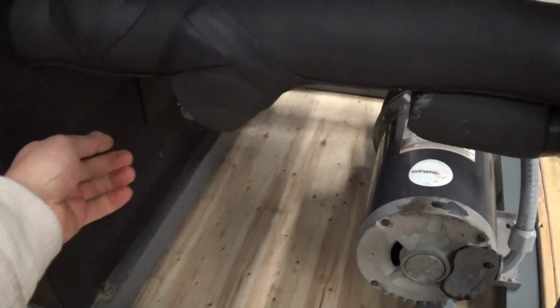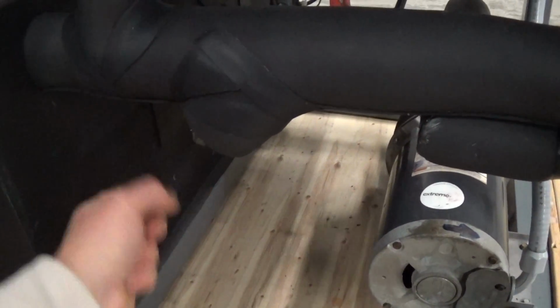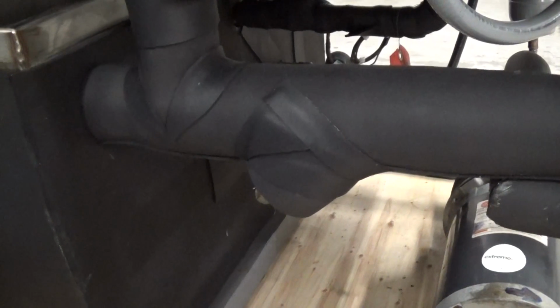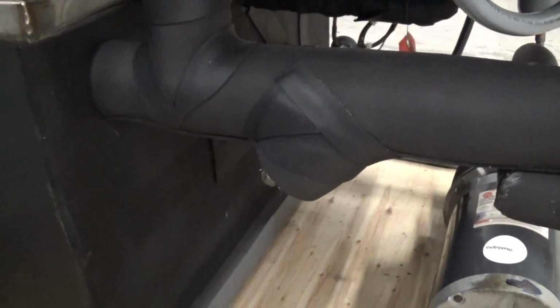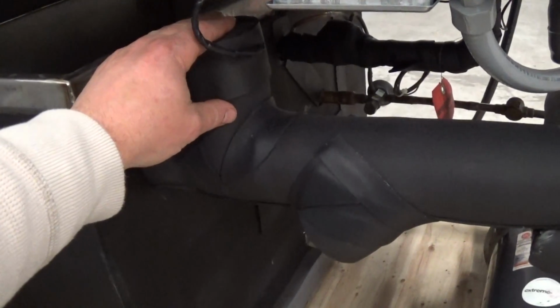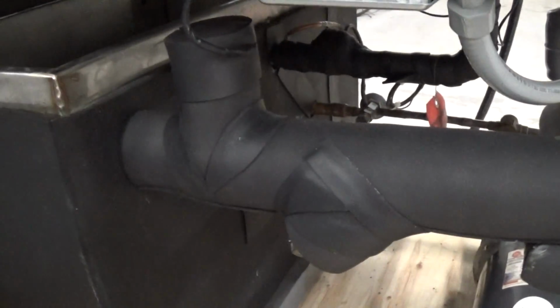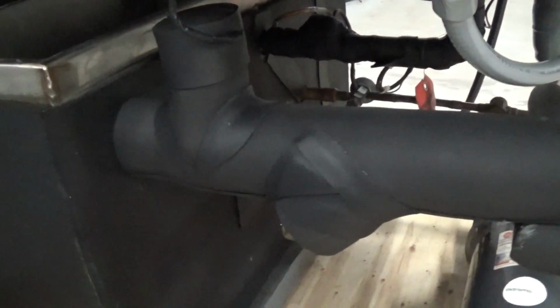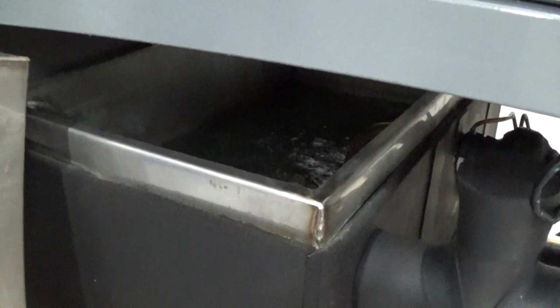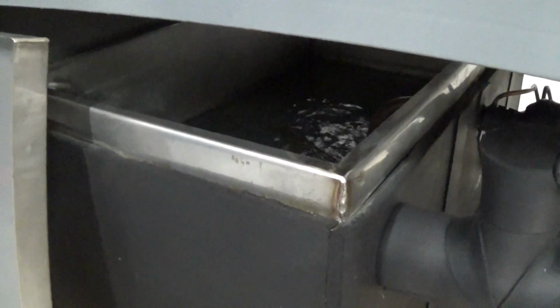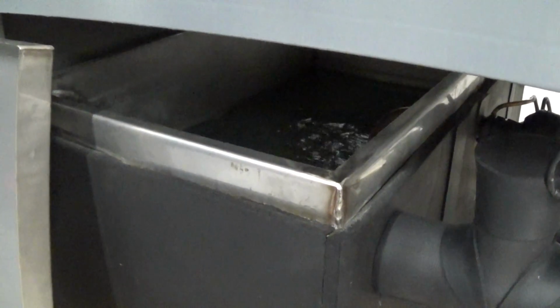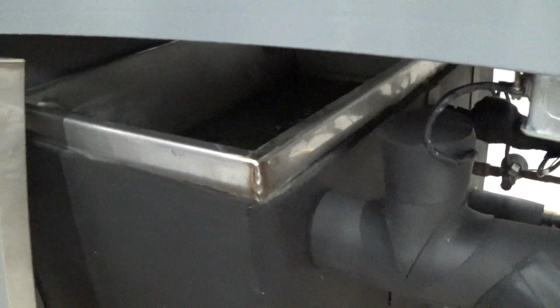You need to take that out regularly just to clean. It's a mesh in there to make sure there's no particulates in the flow. This here is an actual flow switch to make sure we have flow. If we lose flow, the chiller shuts down. This is our stainless steel tank here. This unit has a brand new brazed plate heat exchanger submerged in it, and that's our lid. It'll ship on top of the tank.